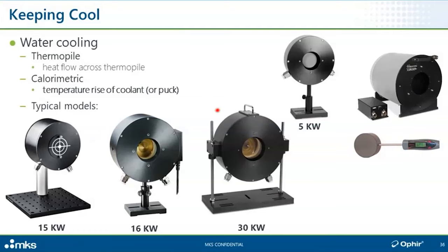You can also see, though, that there are some other configurations. These are all thermopile based. The radial thermopile configuration that we saw before. But here we see something a little different. Here we see some sensors that are calorimetric based, meaning we're measuring the temperature rise of the coolant as an indicator of the power of the beam, or the temperature rise of what we at Ophir call the puck. We expose it to a very tightly controlled exposure time, and the instrument knows the specific heat capacity of the material and so on. So the temperature rise of this puck after exposure of precisely so many seconds is an indicator of the power.